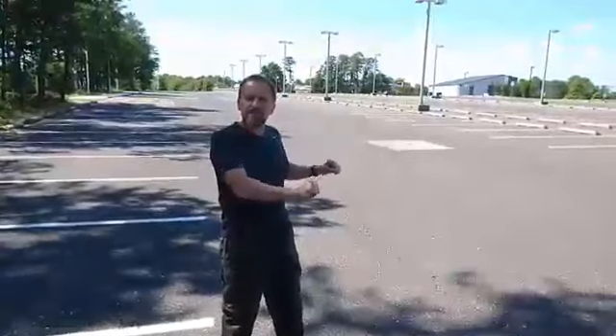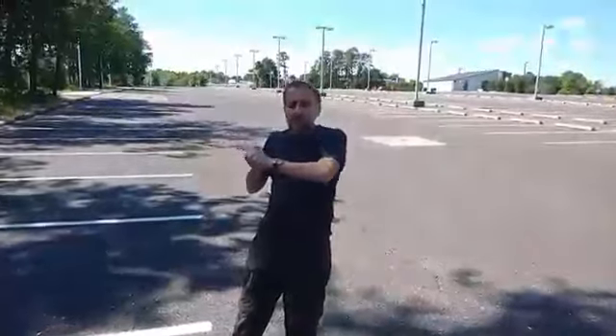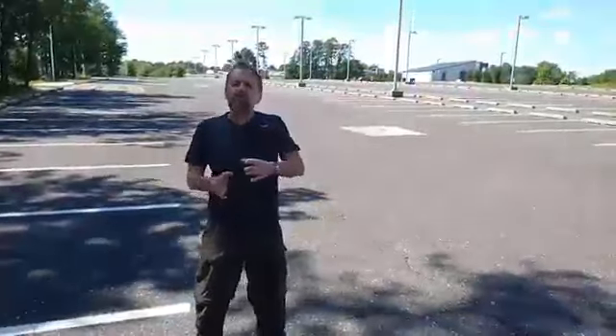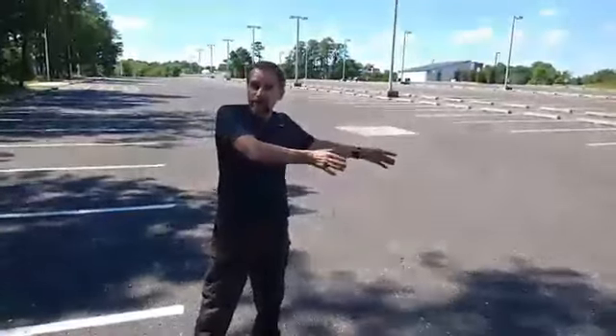The ground temperature is about 59 degrees. So instead of taking outside air that's really cold in winter and really hot in summer and bumping that up or down for heating and cooling, we can take a consistent, steady 59 degrees from the ground and feed that into our heat pump. So when I'm trying to keep you warm in winter, I don't have to start with 5-degree air—I can start with 59-degree air, which is a lot easier to work with, so I use less energy. It dramatically increases the efficiency of the unit. That's why engineers don't call this geothermal, we call it a ground-source heat pump, because it's a heat pump using the ground temperature as its source.